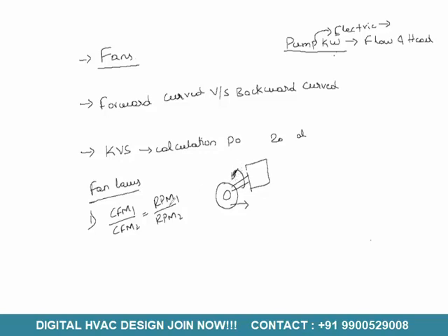So what this law says is, for example, when RPM1 is some x, then you will have CFM also as x. When RPM is increased to 2x, then your CFM is increased to 2x.